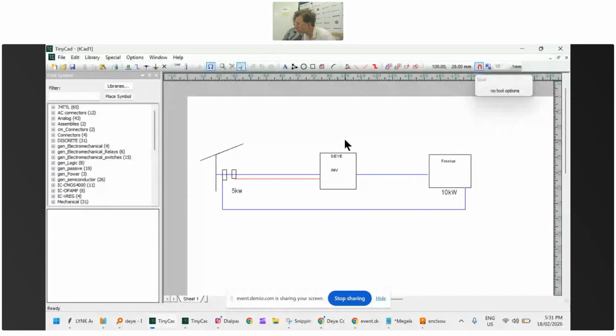There was a question here. In off-grid, should we avoid AC coupled solar to avoid backfeed into the generator? There's a few different ways you can go about that. One good way of doing it is just to set the frequency of the generator to 52 or 53, so that as soon as the generator starts up and the Deye synchronizes with it, that just automatically shuts the AC coupled inverter down.